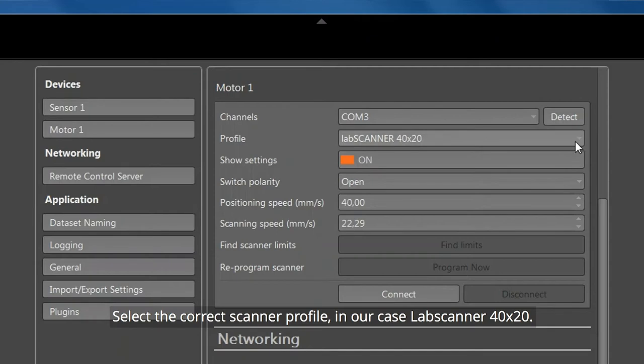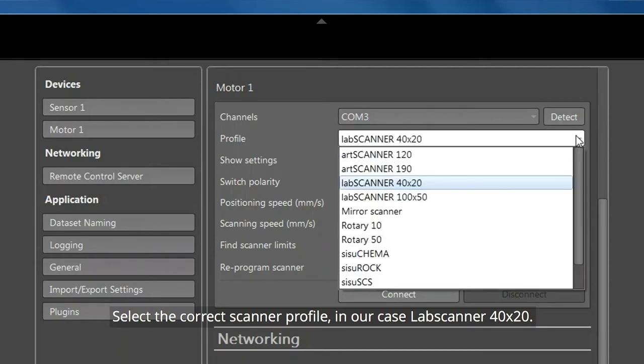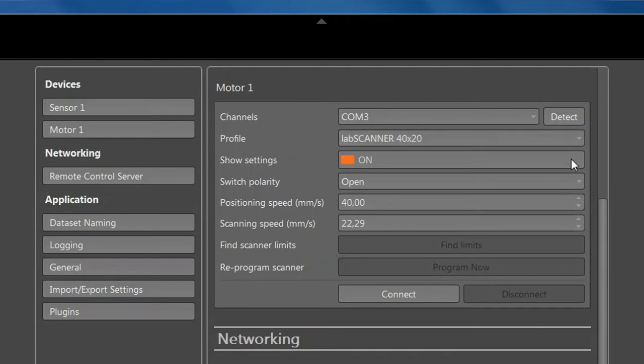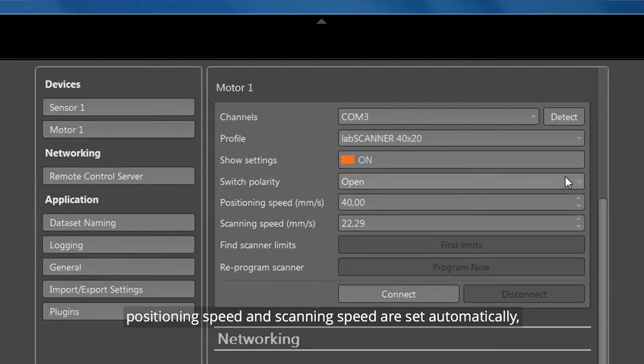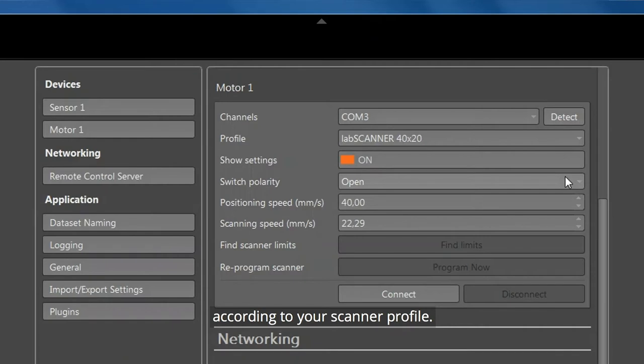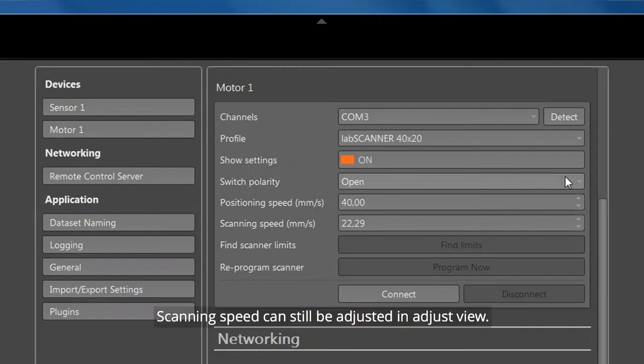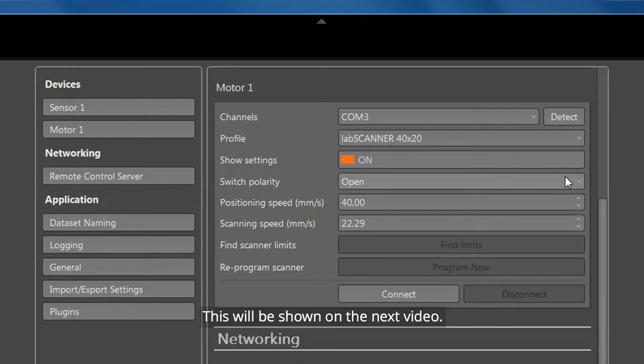Select the correct scanner profile. In our case, Lab Scanner 40x20. Switch Polarity, Positioning Speed, and Scanning Speed are set automatically according to your scanner profile. Scanning speed can still be adjusted in Adjust view. This will be shown in the next video.